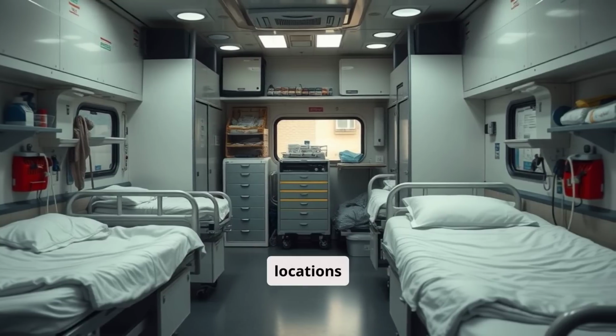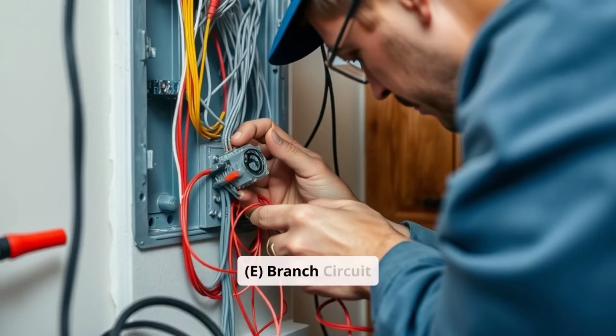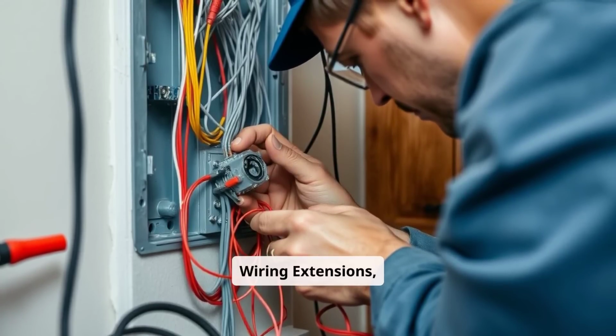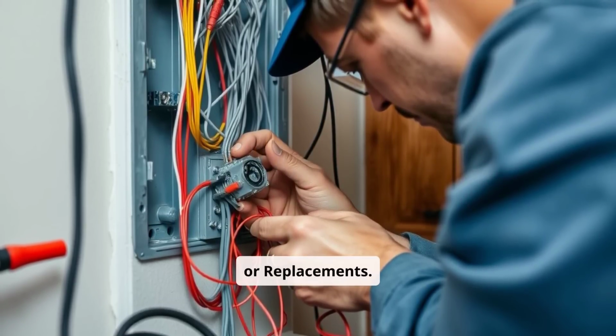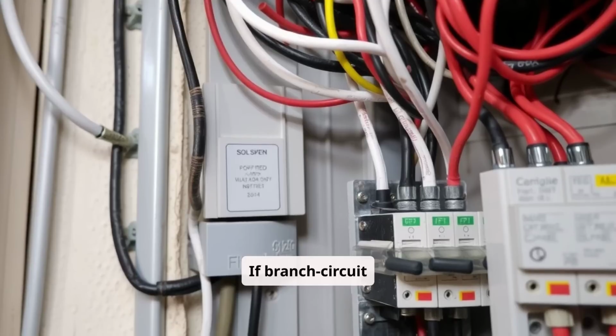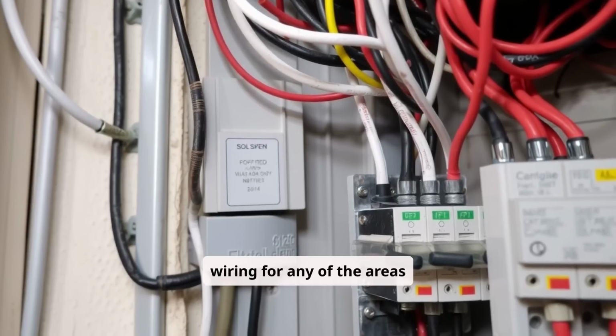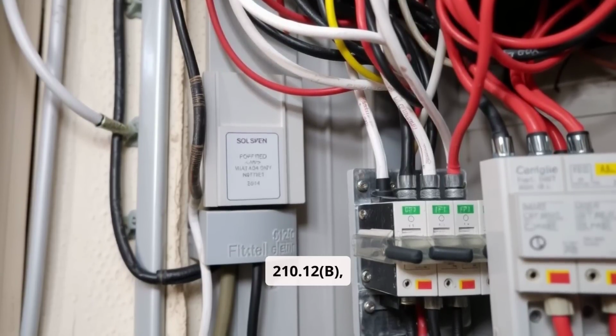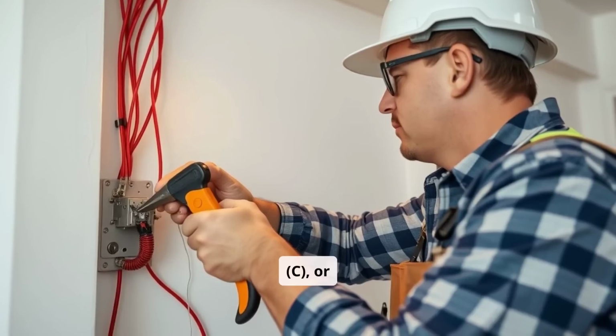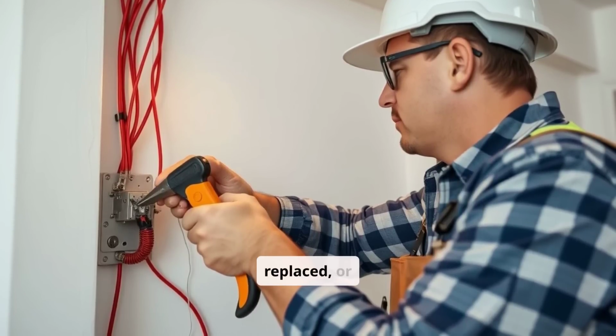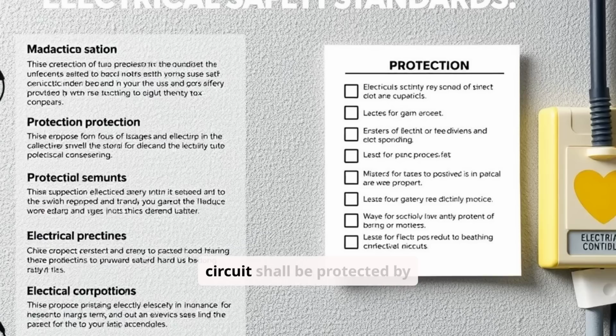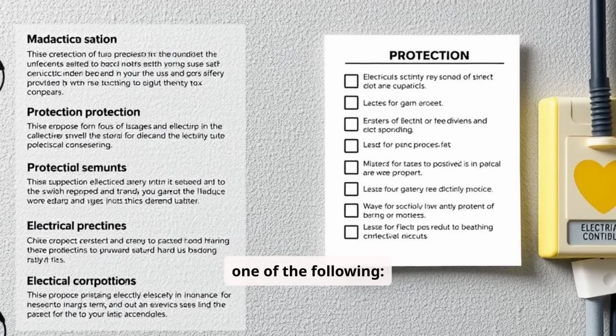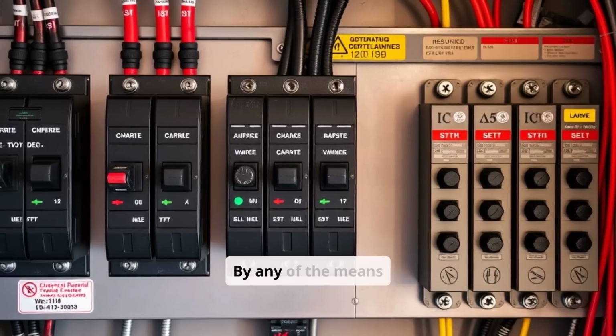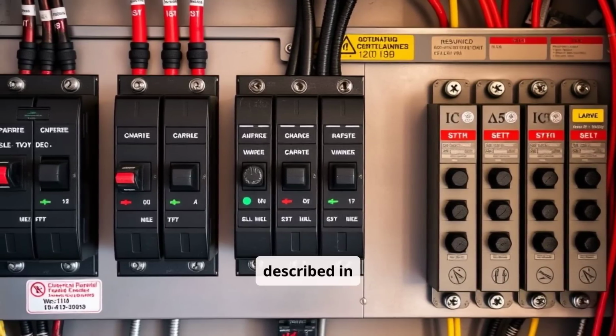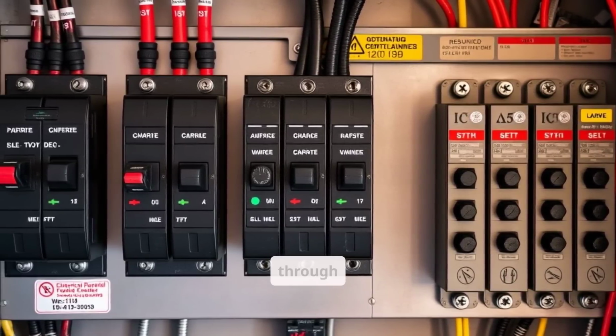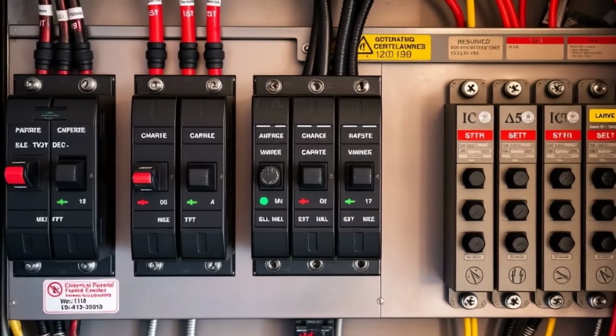E. Branch circuit wiring extensions, modifications, or replacements. If branch circuit wiring for any of the areas specified in 210.12(B), (C), or (D) is modified, replaced, or extended, the branch circuit shall be protected by one of the following: 1. By any of the means described in 210.12(A)(1) through (A)(6).